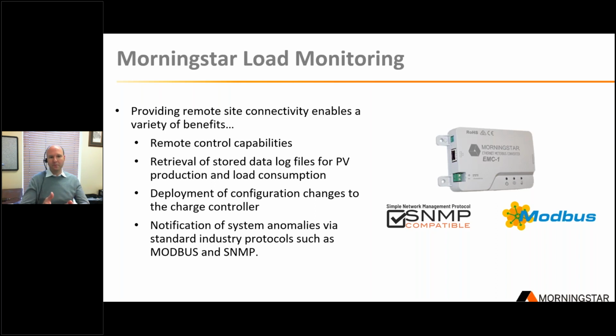So you get remote control capabilities, you can retrieve the stored data logging files, you can do your own real-time logging, and you can even set up notifications to inform you of pending system problems before they lead to system failure. And the two major protocols that we support are SNMP, which is Simple Network Management Protocol. Anyone in the IT or communications or telecom space, that's really their go-to for managing the network. And now you can use it to manage the controller as well, all in the same system.